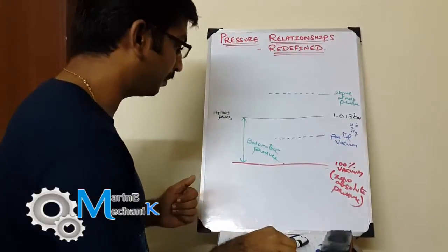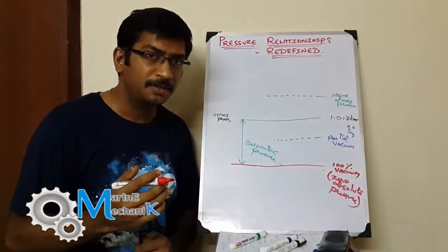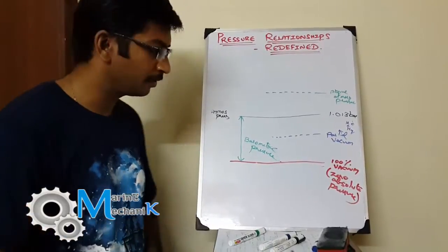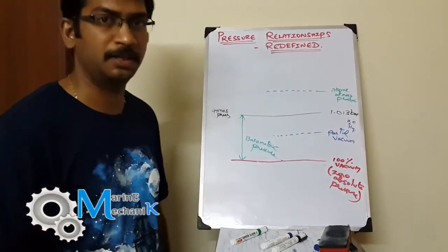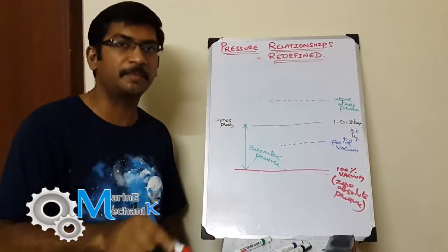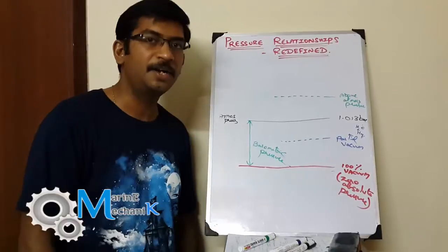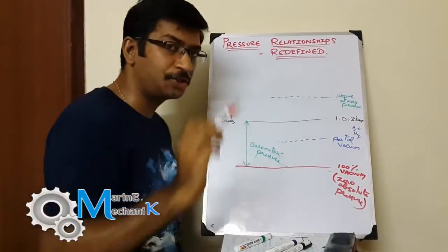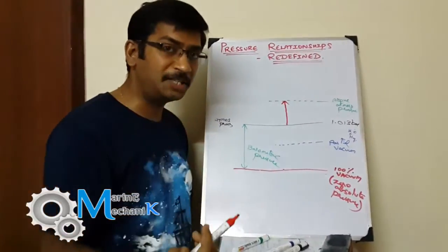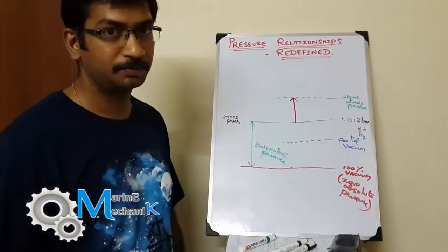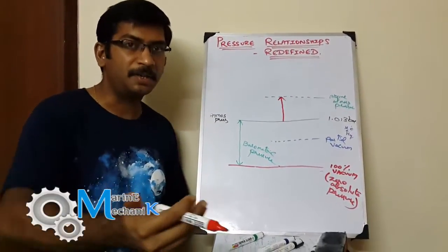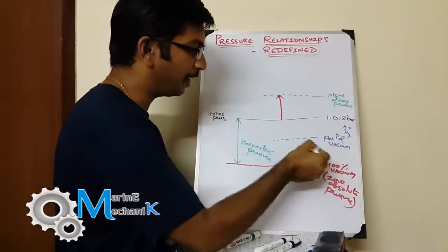Gauge pressure is simply what is shown on a gauge. But what does the gauge show? It cannot show zero absolute pressure, and it also cannot show atmospheric pressure directly, because the Bourdon tube inside the gauge is manufactured under atmospheric pressure. Therefore, the gauge can only read pressure above the atmosphere. However, some gauges are designed to read negative pressures — that is, the partial vacuum zone.